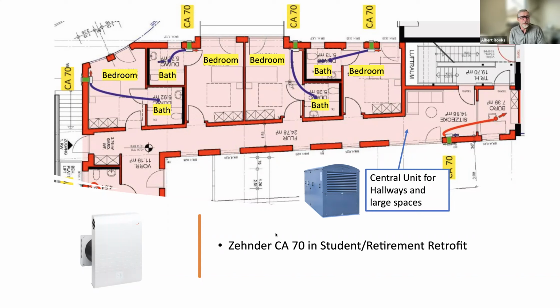And then for the hallways and the large spaces, I'm just suggesting, I just grabbed a big ventilation device from Ventacity, just something that does 1,000 CFM or something like that. Park it up in one location, try to duct down and get into all the common hallways and corridors and so forth, whatever's possible. There are units that are sized that can be just set in the top of a corridor and just take care of that corridor, or you can try to tie all the corridors together with a riser and connect them to a large unit. And so there's a way we could actually do a whole building right there.